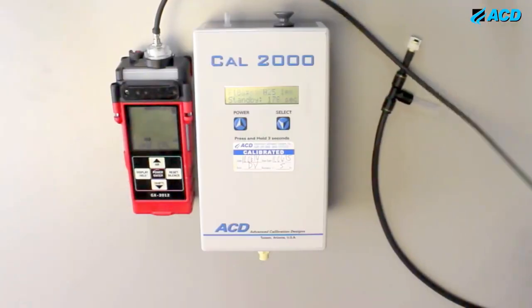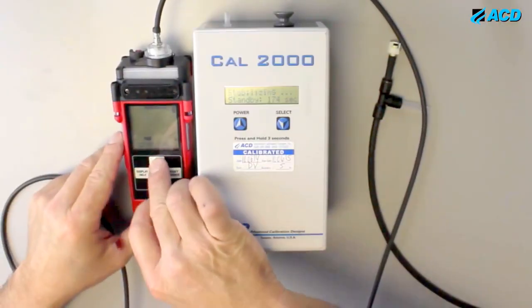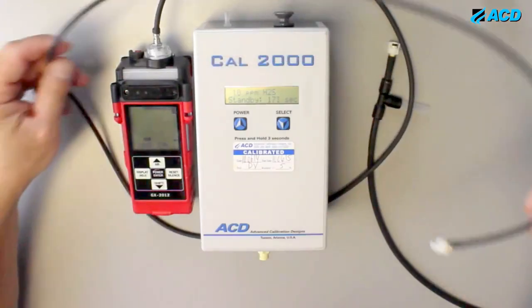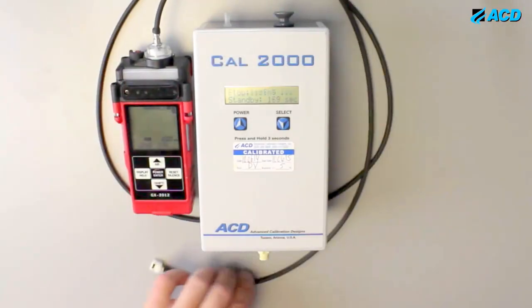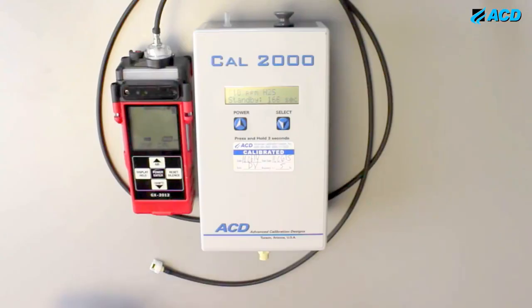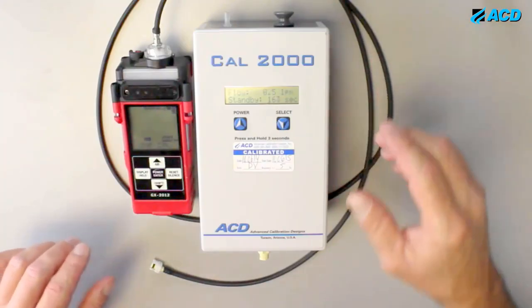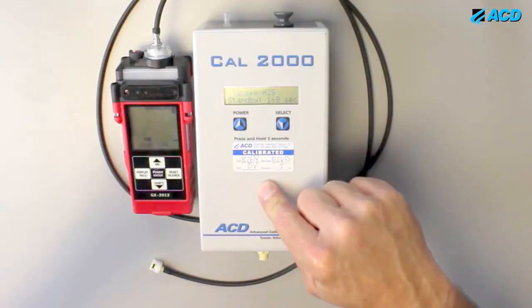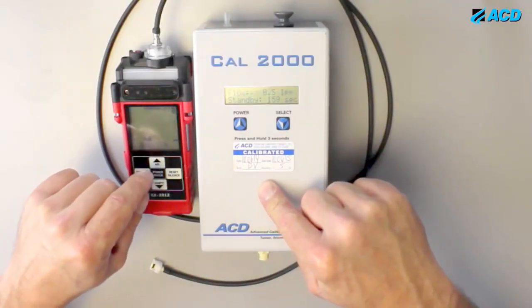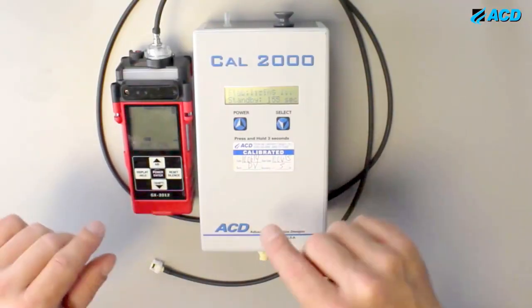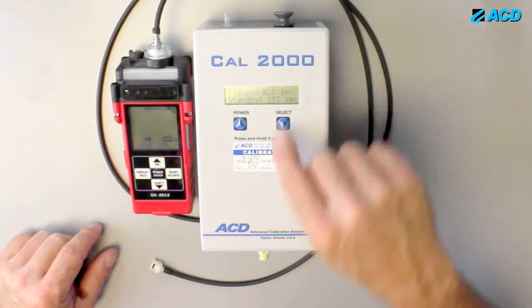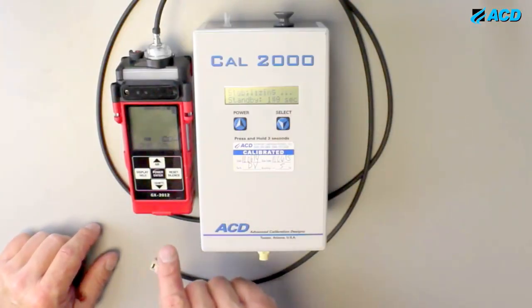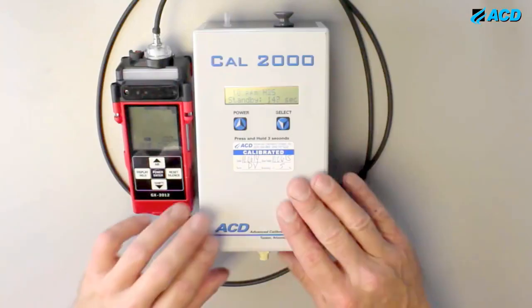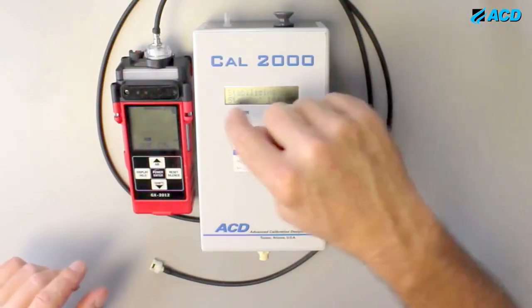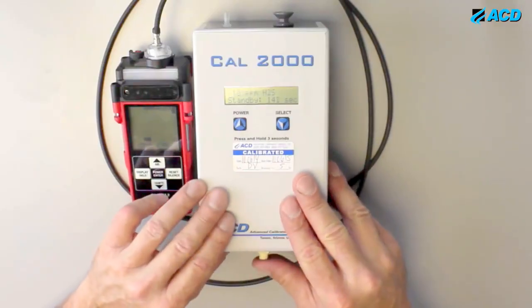And this right here, I've got a GX 2012, and it is already in the calibrate mode, and it's got an internal pump, and it flows at about 0.35 liters per minute. Now, because the Cal 2000 has a pump and the sensor, this GX 2012 has a pump, they would fight each other. So if I've got this set to 0.5 and I've got this set to its sample drawing rate of 0.35, what you will get is you'll get a flow failure out of your Cal 2000. So I'm going to simulate that.